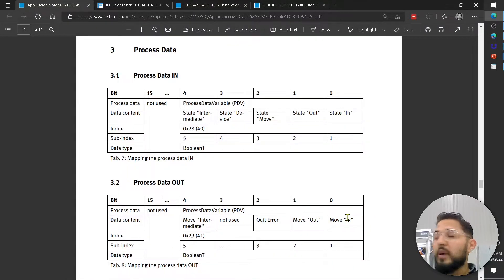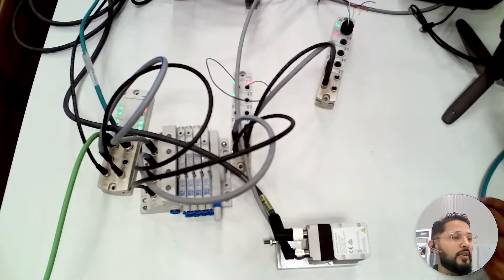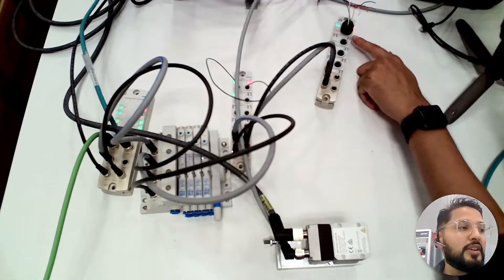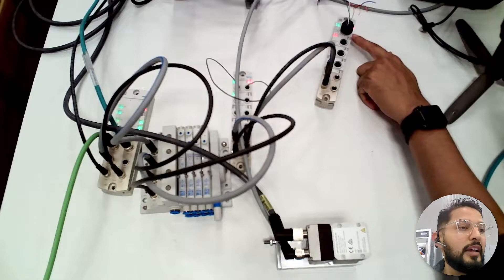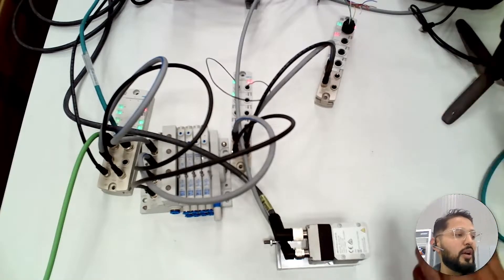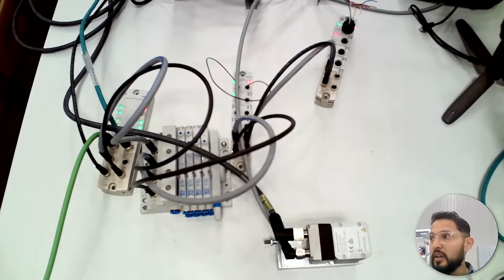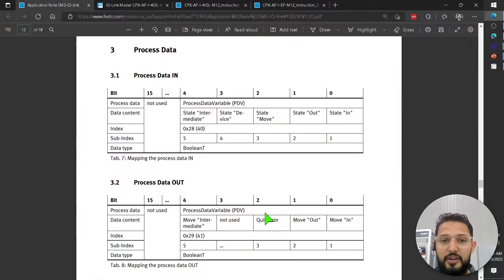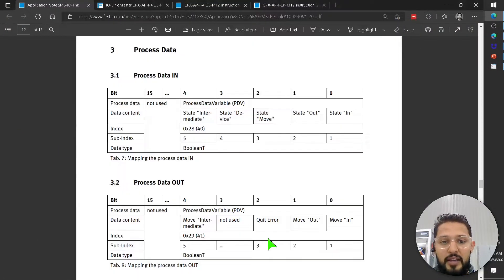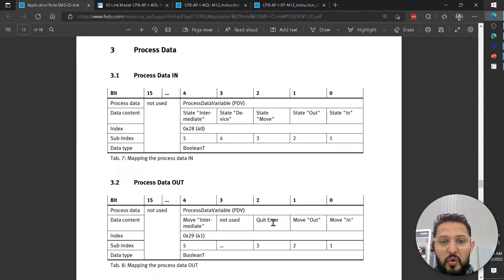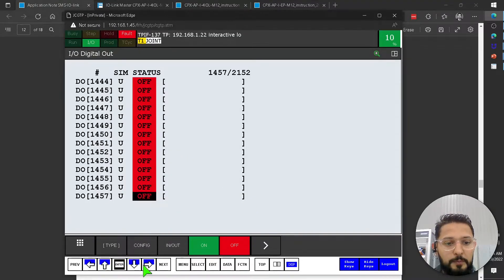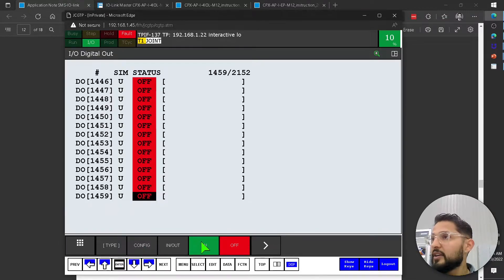But right now I have a fault. I don't know if you can see it there. There's a red LED here. This is actually flashing as well. And there's a red LED on the device as well. I'm going to clear that error using this third bit, quit error, clear error. So 1, 2, and 3. I'm going to clear that error.